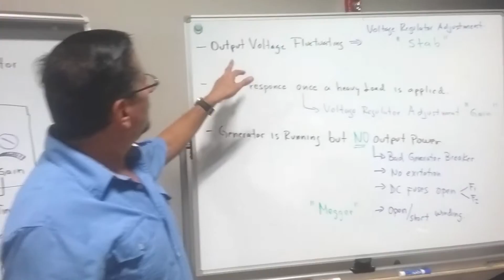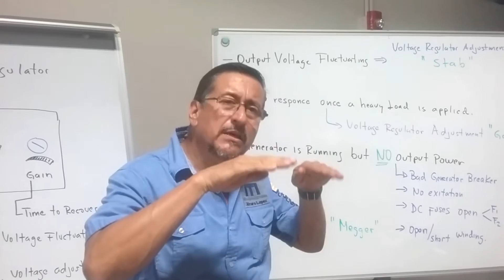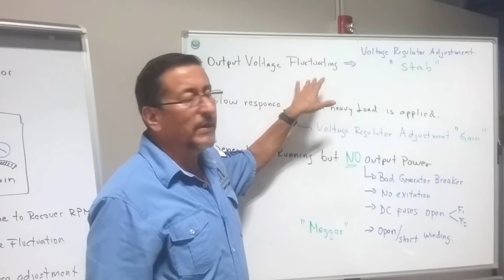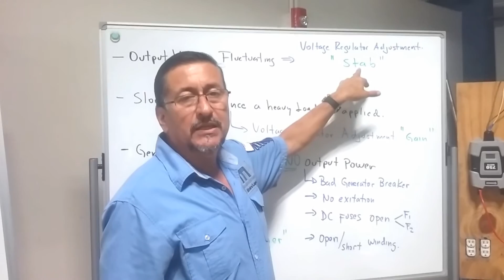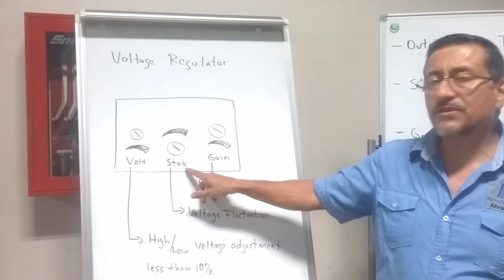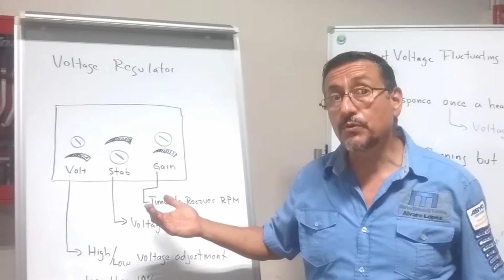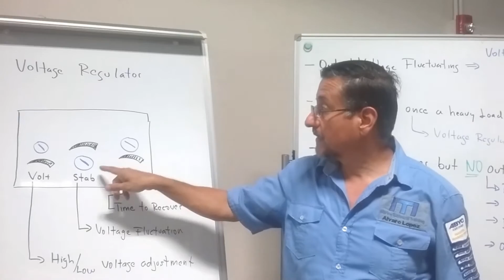Okay, another typical problem is output voltage fluctuating. The output voltage is not stable, it is increasing and decreasing. That problem can be solved on the voltage regulator at the stabilization spot. Normally the second spot is stabilization. If you adjust that spot with the generator running, producing power, you can stabilize the output voltage.